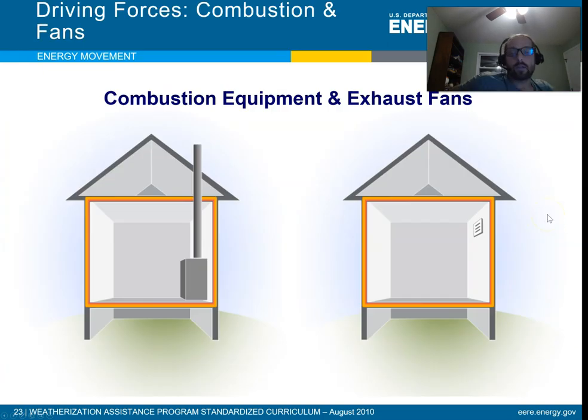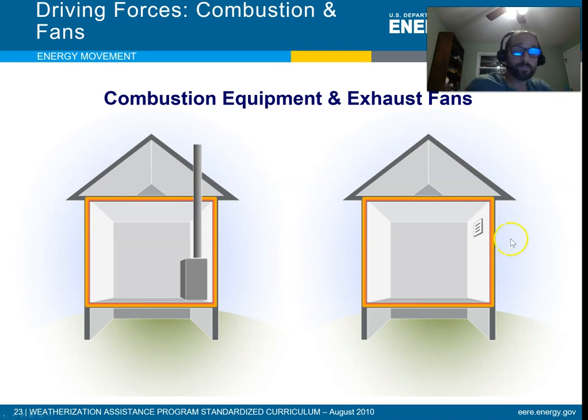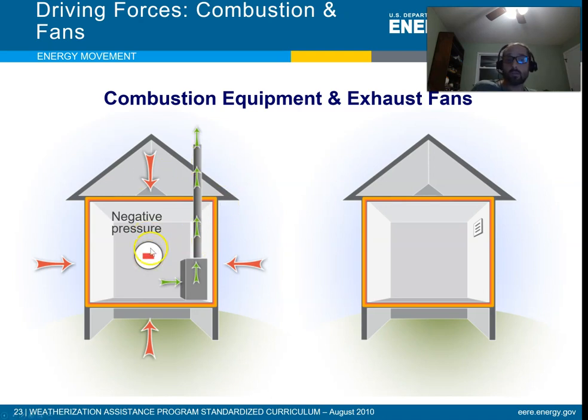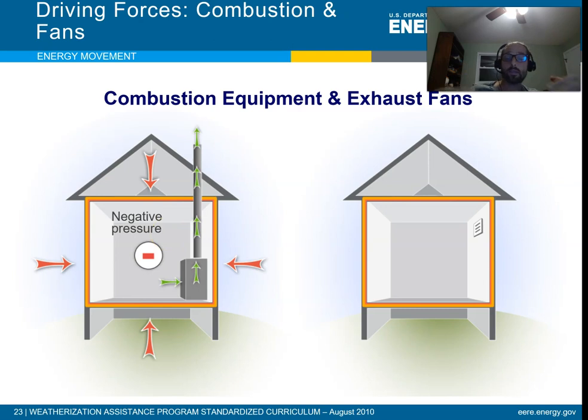Other ways that air moves in and out of a building — things that can change the pressure regime inside — include exhaust fans and furnaces. A furnace in a basement draws air in for combustion and expels it through the flue, so air is leaving the building, which means air has to come in somewhere else.